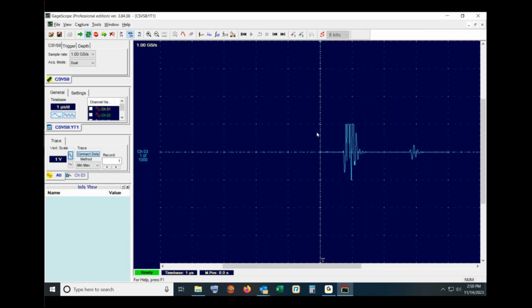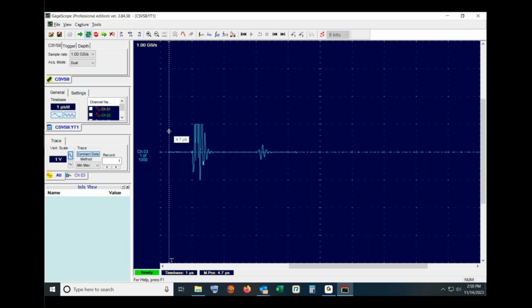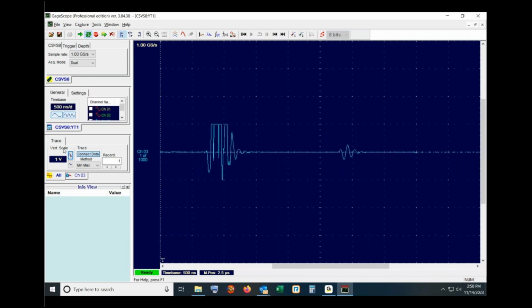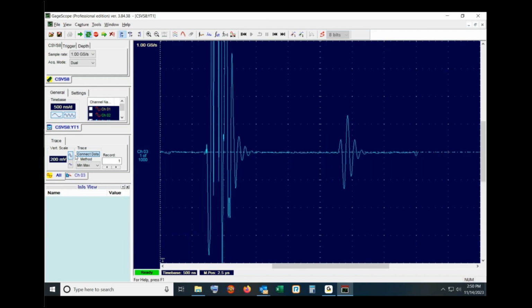So you see, as I said, I acquired 1,000 waveforms with a trigger rate of something like 350 hertz, 350 triggers per second. So as a result, I acquired for about 3 seconds. I scrubbed the transducer across those 3 holes in 3 seconds. So let me zoom in horizontally and vertically. And the first thing I want to show you is to prove to you that I'm really acquiring at that fast trigger rate.